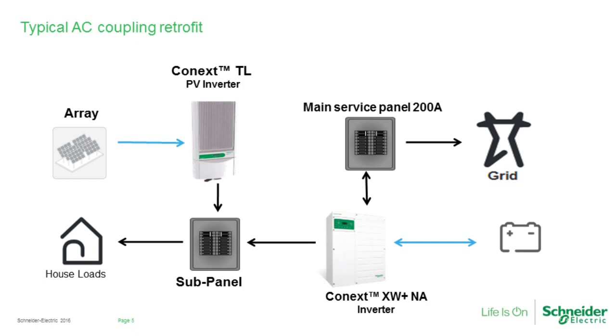And with AC coupling, we're pushing power through the grid forming inverter onto those batteries during a power outage. And unfortunately, that doesn't necessarily leave us with the best charging characteristics. There are certain advanced technologies that aren't going to like that very much. We'll touch again on that a little bit later. But DC coupling definitely brings the best solution possible for that system. So let's examine what an AC coupling retrofit looks like.